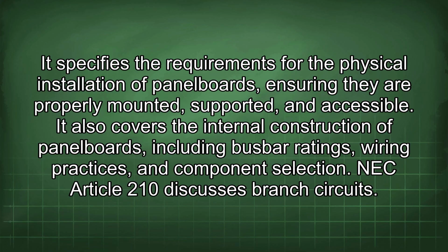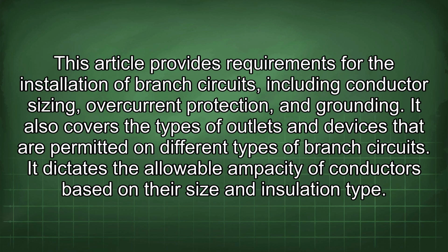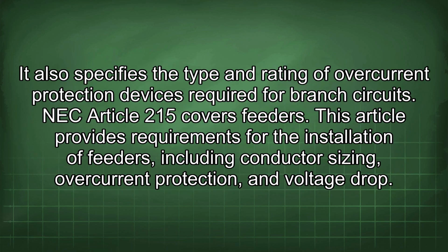NEC Article 210 discusses branch circuits. This article provides requirements for the installation of branch circuits, including conductor sizing, overcurrent protection, and grounding. It also covers the types of outlets and devices that are permitted on different types of branch circuits. It dictates the allowable ampacity of conductors based on their size and insulation type. It also specifies the type and rating of overcurrent protection devices required for branch circuits.